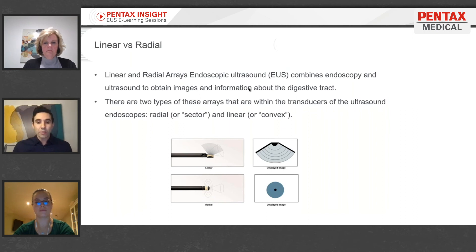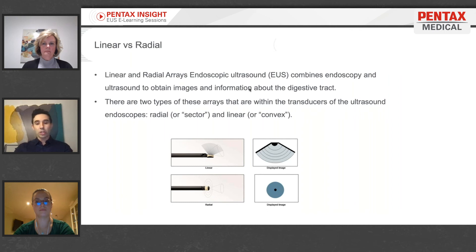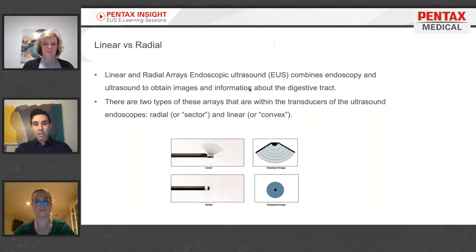The 360-degree imaging gives you a very logical approach to visualization. For example, when you're in the esophagus and you put the aorta on the left, you know what should be on the right side just by virtue of thinking of yourself in a cylinder looking around. The linear scope, on the other hand, is a little different. The best way to describe it is a swimmer in a pool with their head looking toward the bottom — you don't see to your sides or above, but you're looking at the pool floor, and if there were something to grab, you could reach down. That's the convex imaging you obtain with the linear endoscope.